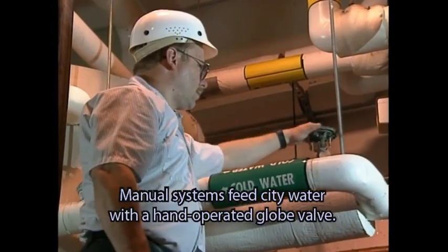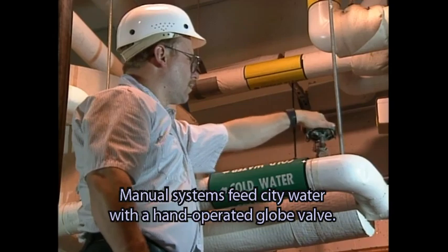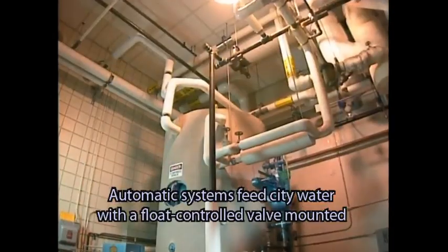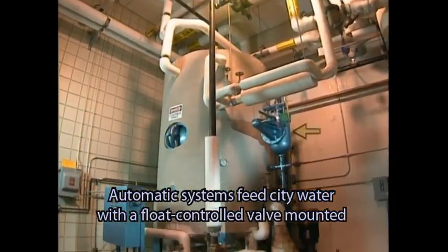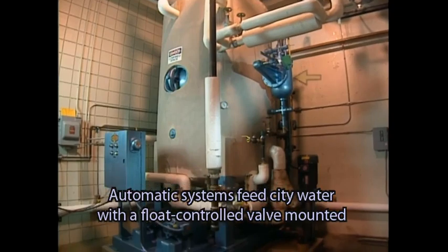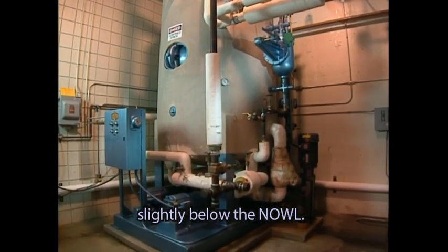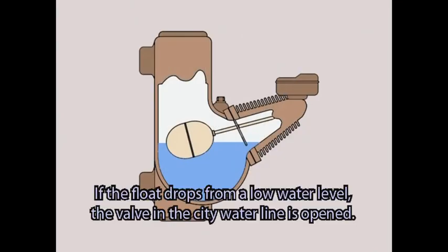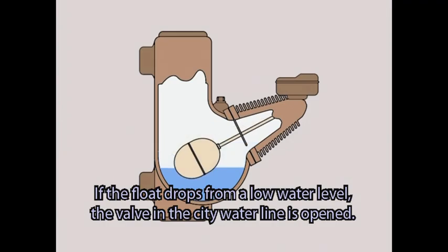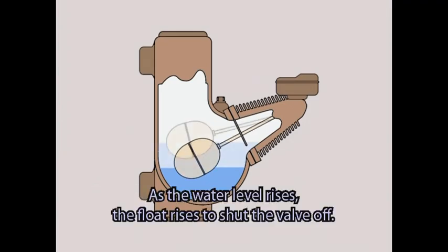Manual systems feed city water with a hand-operated globe valve. Automatic systems feed city water with a float-controlled valve mounted slightly below the NOWL. If the float drops from a low water level, the valve in the city water line is opened. As the water level rises, the float rises to shut the valve off.